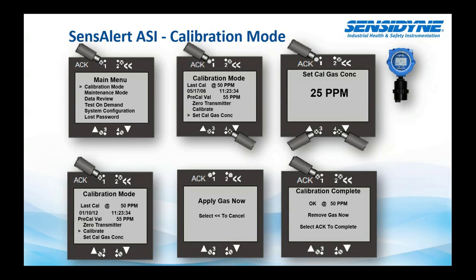Once the calibration is complete, it'll give you an okay, pass or fail at 50 ppm, and then tells you to remove the gas and select acknowledge to complete. And that's it, you're done. It takes a few minutes. Basically you just gotta go through three menu steps, I should say. Apply your gas, turn your gas off, and you're ready to go.